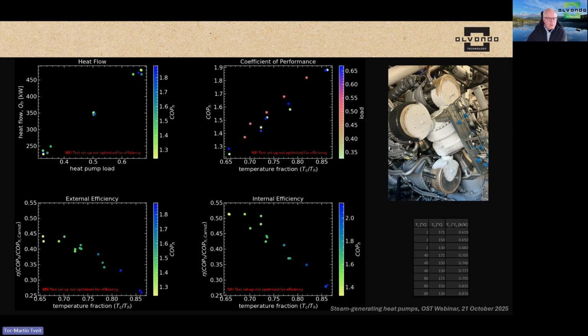You can also see the internal efficiency, which is the efficiency of only the heat pump with the auxiliary pumps, but not any of the pumps needed to transfer water to the heat pump. Then you have the external efficiency, where all the circulation pumps are also included. You can see this is maybe not so linear, but that's probably more due to the setup of our test than anything else.